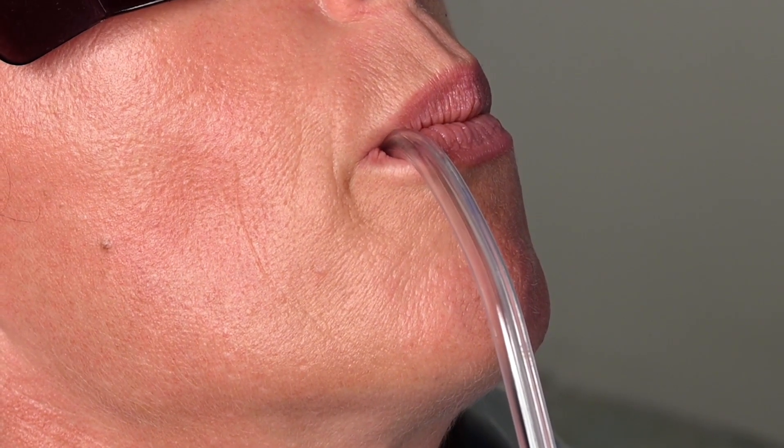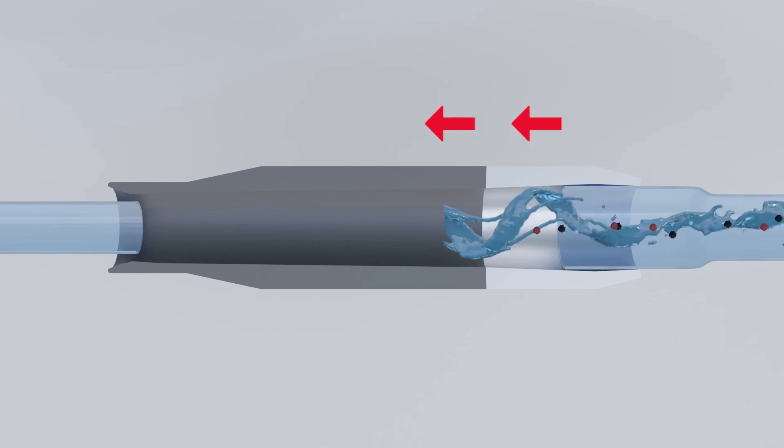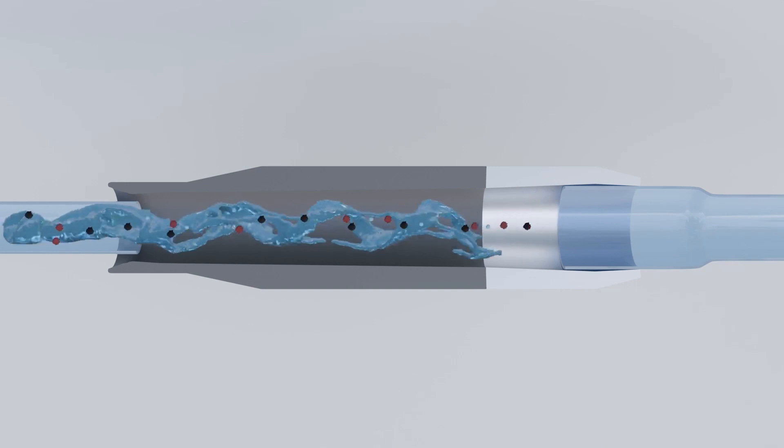When a patient closes their mouth around the saliva ejector, the pressure in the vacuum drops, increasing the risk of contamination being pushed back into the mouth. This could lead to transmitting pathogens and other biological material from the previous patient, thereby jeopardizing the current patient's health.